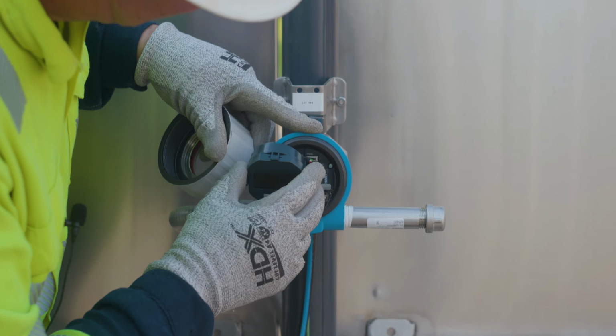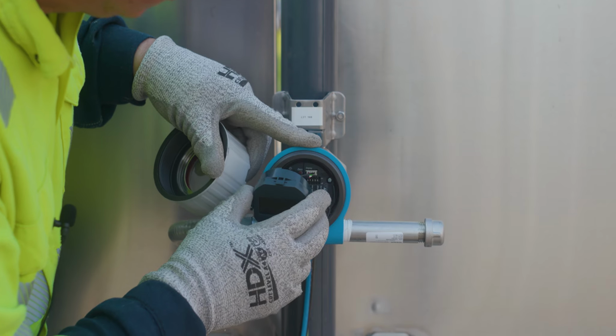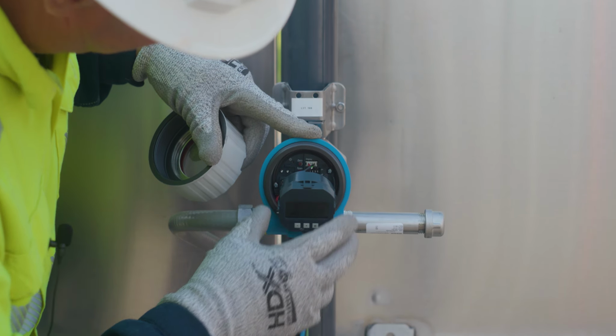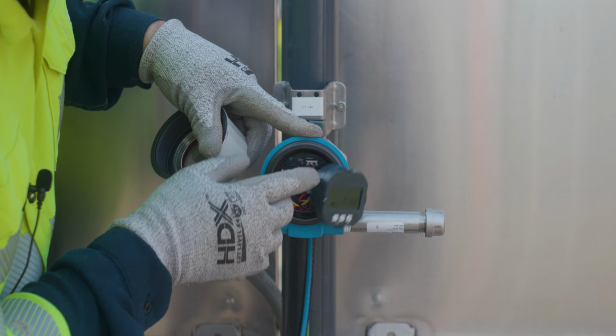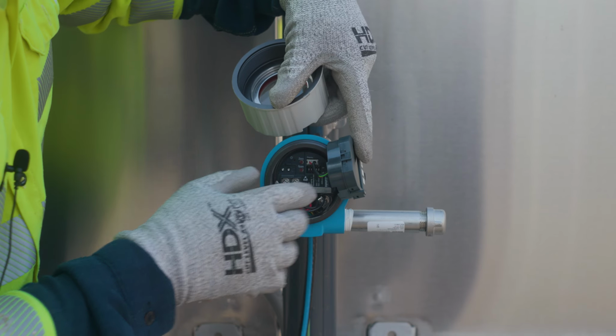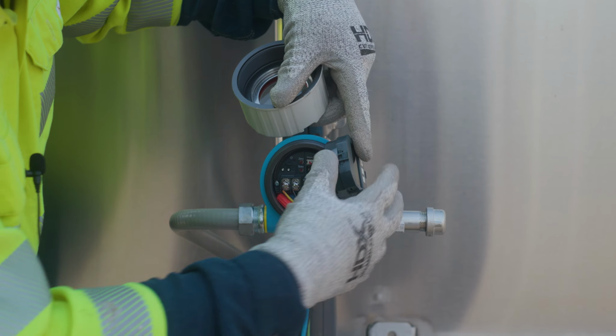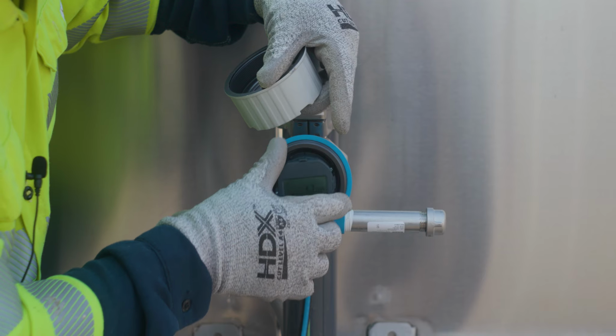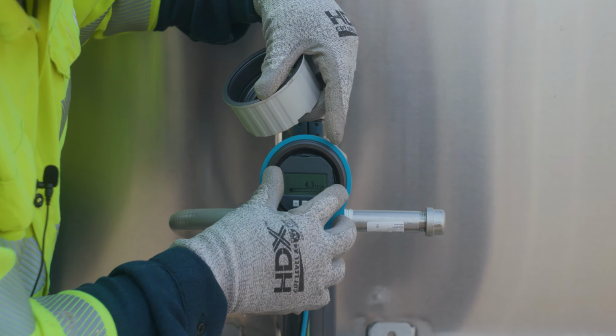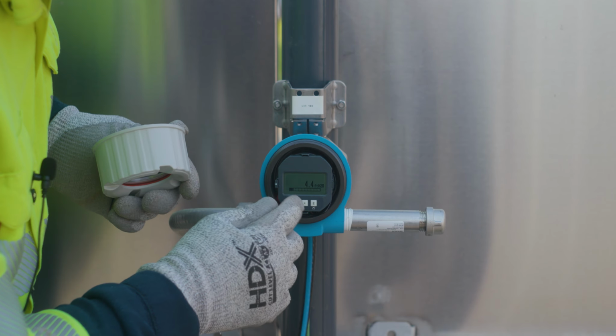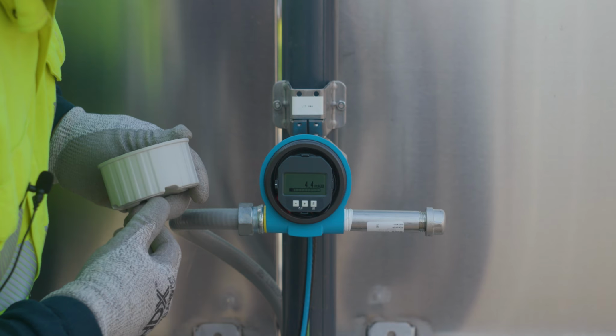and then it has dip switches based on whether you're using current or voltage, and you can also zero the meter out or respan it based on its current connection. But you do have to take this off to operate the menu buttons.